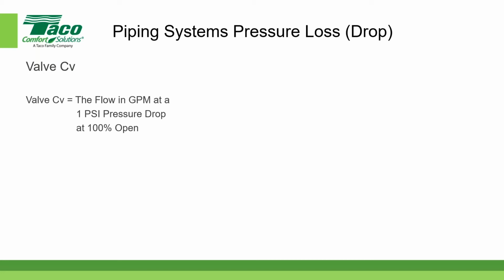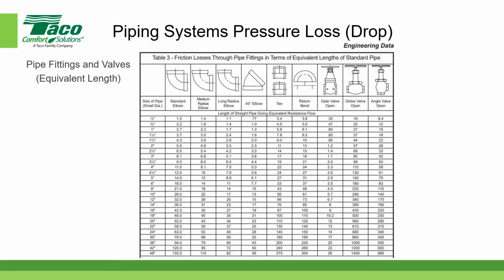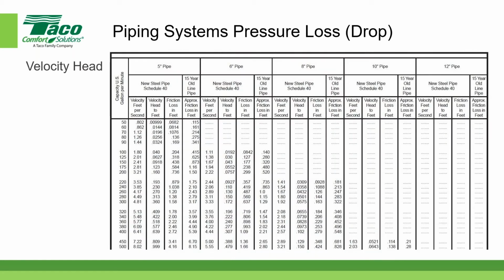Well, the charts that I showed you, let's go back here. Generally speaking, this chart is a fairly common chart that's used in the industry for equivalent lengths of fittings. And the other chart that I showed you, with the exception of the friction loss, let me just highlight that. Depending on, in this third column, which we will touch on in a minute, the friction loss can be higher or lower for a given value. So in our case, we had 500 gallons per minute, and the friction loss would be 4.16 feet per 100 feet.